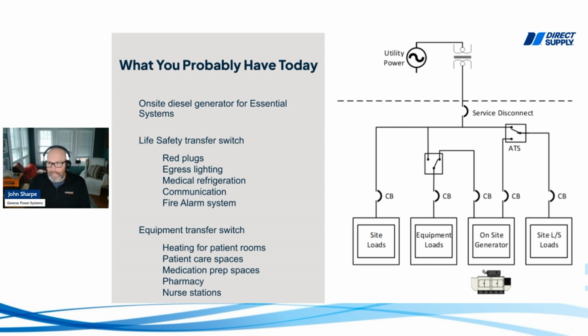One thing I want to point out here: notice there are two different devices called automatic transfer switches - one up here to the upper right, and one here in the middle. Code requires that you separate those loads. That's a code done nationally per the National Electric Code - things taken care of on the life safety side have to be separated from things on the equipment side, because if something happens on the equipment side, we want to make sure we have what's called separation of circuits.